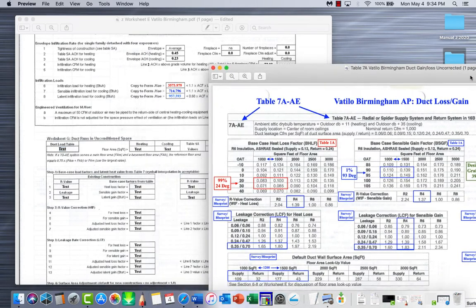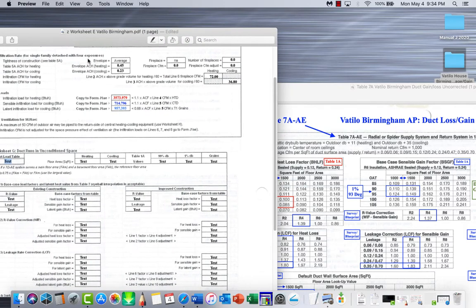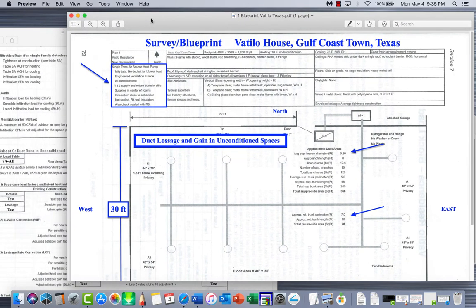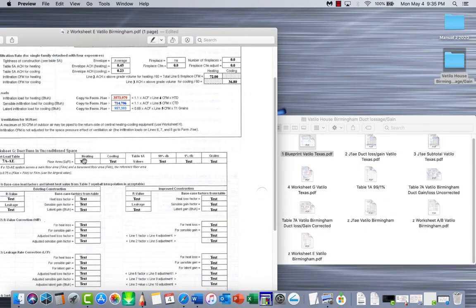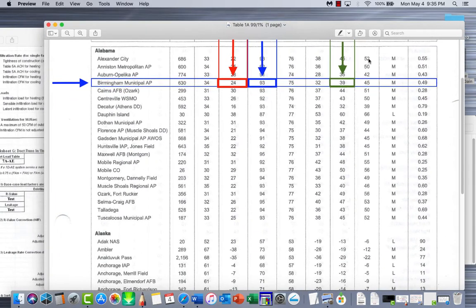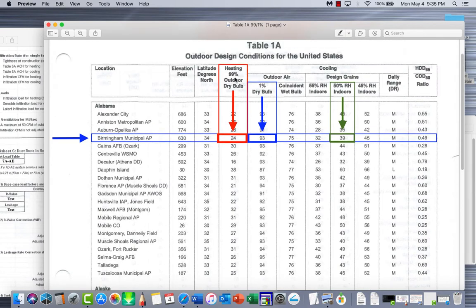Our first construction number is going to be 7A-AE. For square footage, we go back to the blueprint - our blueprint is 40 by 30 for 1,200 square feet. Since we're heating and cooling the same area, both of these square footage numbers are going to be 1,200. Next, we go to Worksheet A or Table 1A. Here we have Birmingham Municipal Airport - that's where all the data at the top of these papers is coming from.